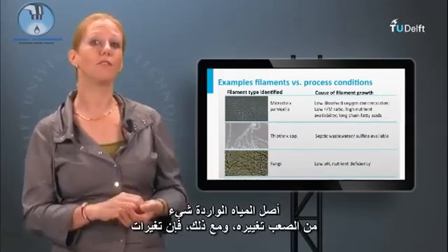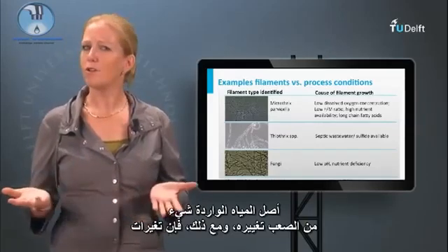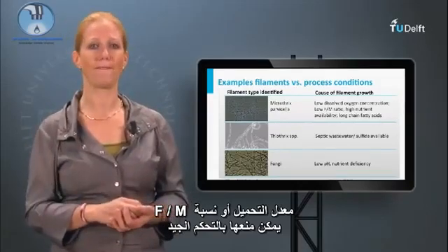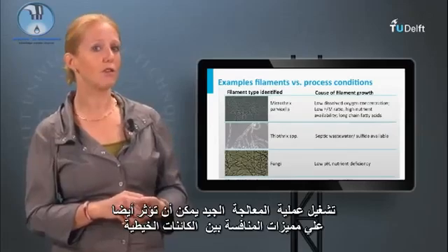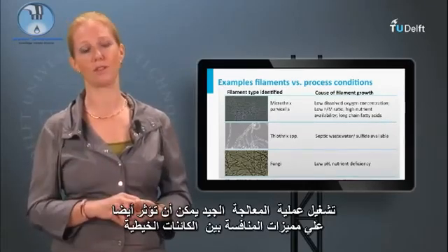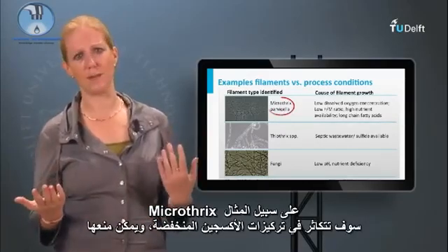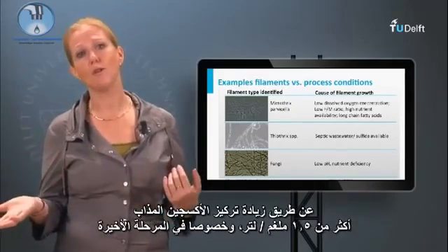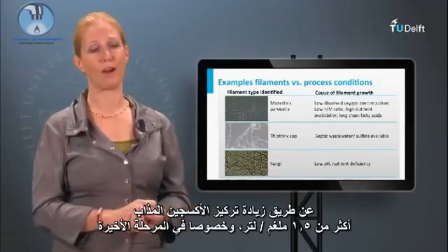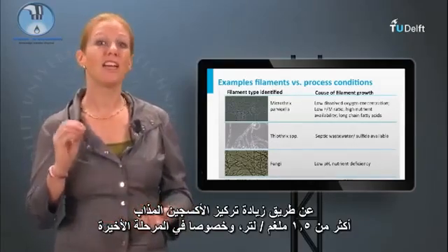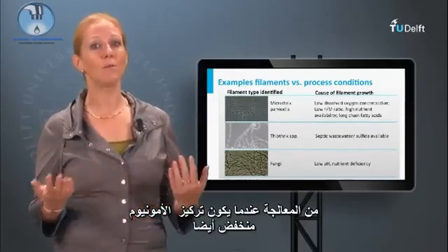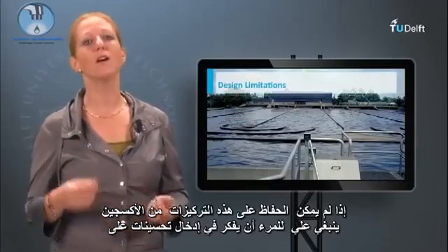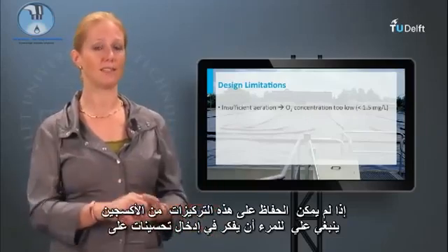The origin of the influent is something that is difficult to change. However, fluctuations in loading rate or food-to-mass ratio can be prevented with good control. Good process operation can also influence the competitive advantage of filamentous organisms. For example, Microthrix species will proliferate at low oxygen concentrations and can be prevented by increasing the dissolved oxygen concentration over 1.5 mg per liter, especially in the last phase of the treatment when ammonium concentrations are low as well. If these oxygen concentrations cannot be maintained, one should consider improvements on the existing aeration system.